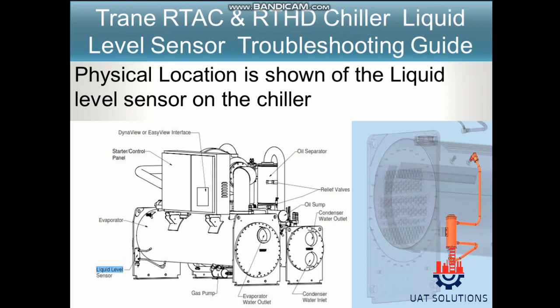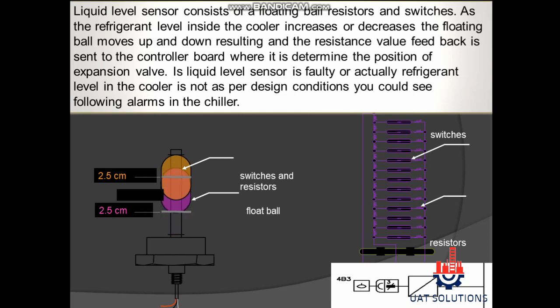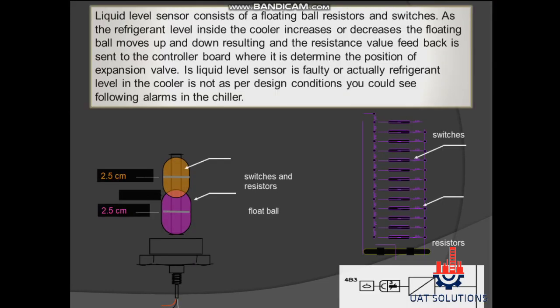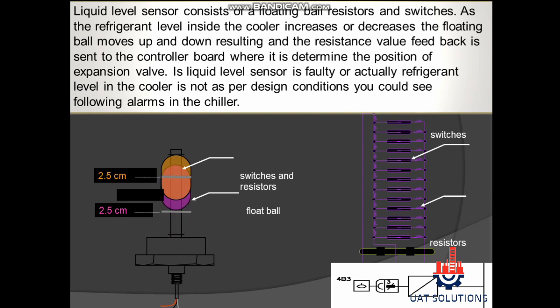The physical location of the liquid level sensor on the chiller is shown. The liquid level sensor consists of a floating ball, resistors, and switches. As the refrigerant level inside the cooler increases or decreases, the floating ball moves up and down, and the resulting resistance value feedback is sent to the controller board, where it determines the position of the expansion valve. If the liquid level sensor is faulty, or the actual refrigerant level in the cooler is not as per design conditions, you could see the following alarms in the chiller.